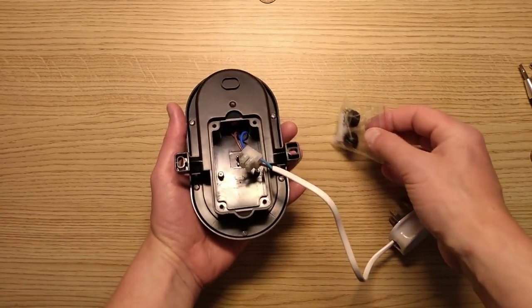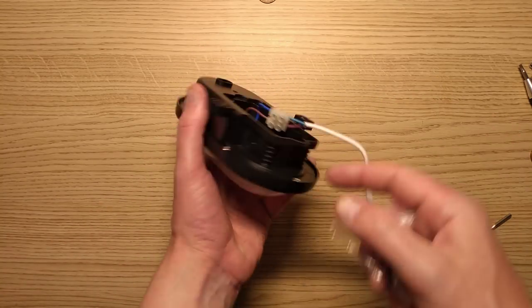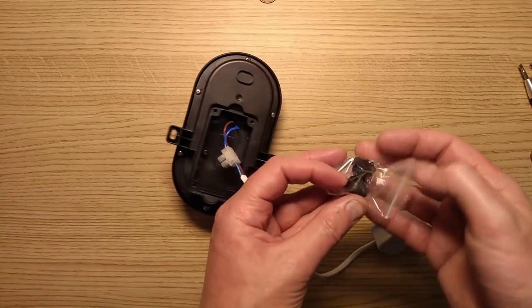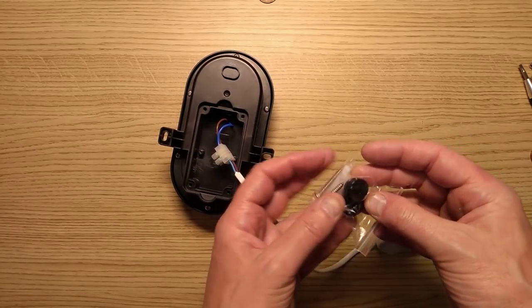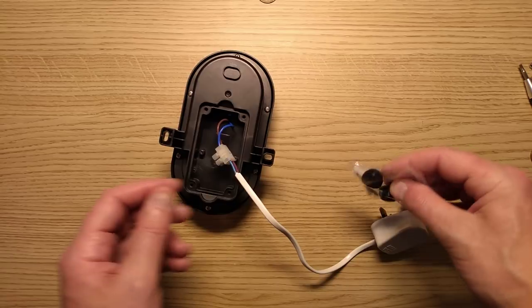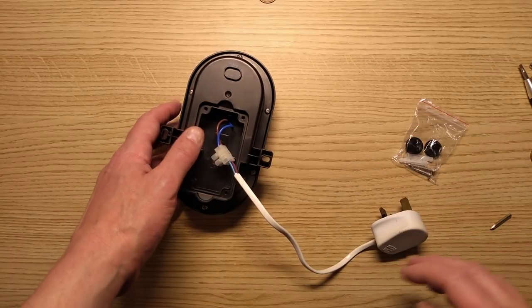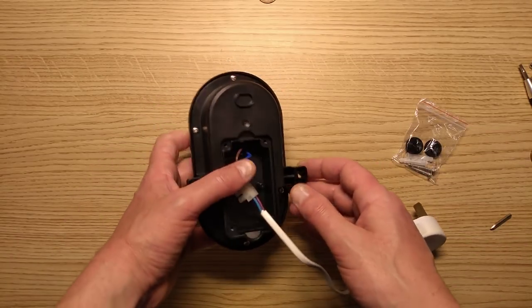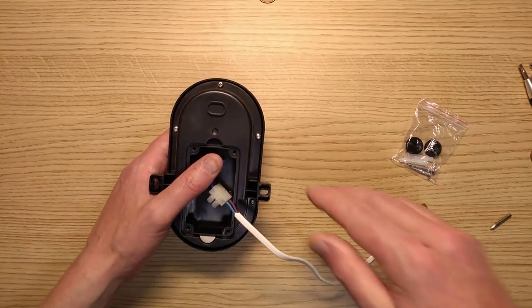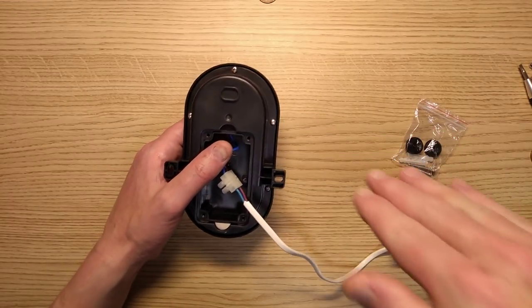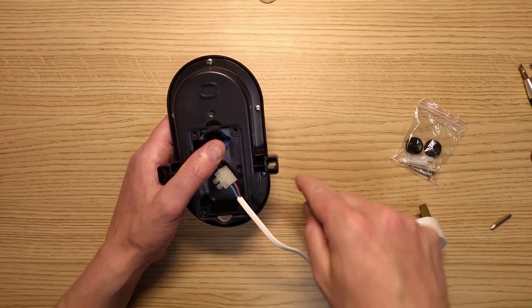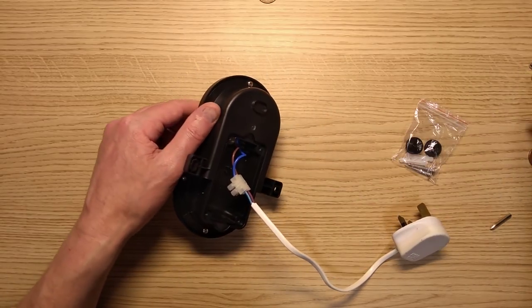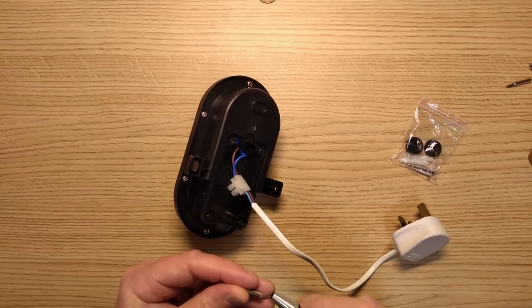Other things worth mentioning are that it does come with little knockouts on the side with plugs that go into those. It specifically mentions not to use flat cable like twin and earth. They also go into detail in the instructions about drilling holes diagonally down as you're going out of your building, drip loops. It's quite a comprehensive set of instructions.